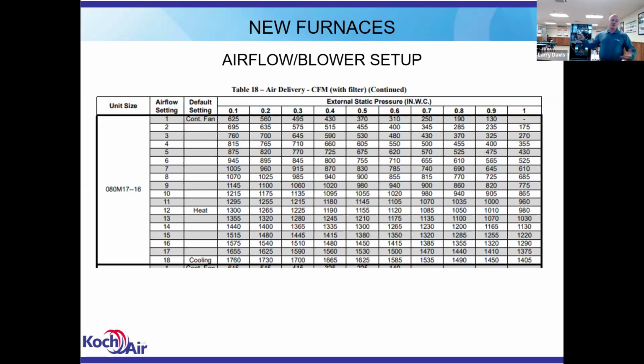If I'm measuring a different static pressure, then I'm going to have to make a change in my fan speed setting to get it to where I need it to be. Just remember, every time you change that fan speed, it changes the static pressure. So it's a little bit of a moving target. You just kind of have to fine tune it, narrow it down, and get it where you want it.